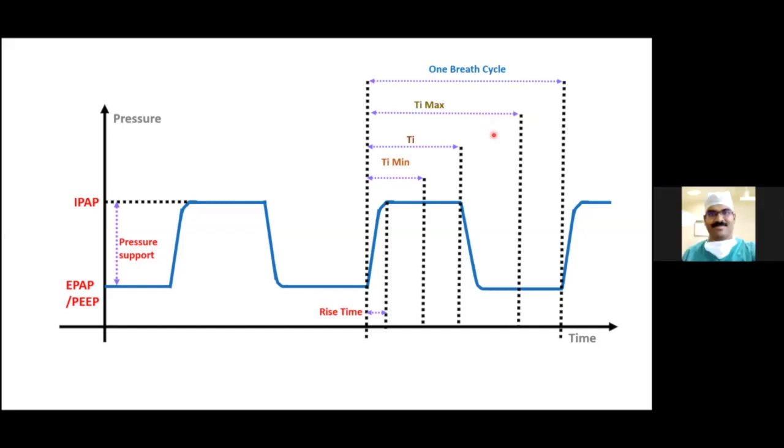Sorry, can I interrupt? There are some queries regarding rise time again. The rise time, otherwise called the ramp. You can see the inspiration starting from here, and this is reaching the maximum point, the maximum flow. The time required to achieve the maximum flow is called the rise time.